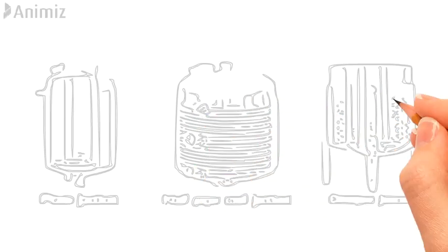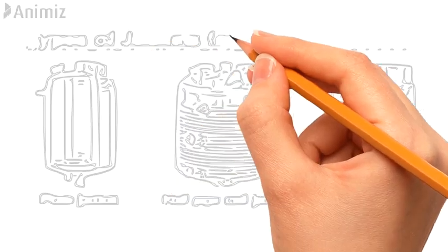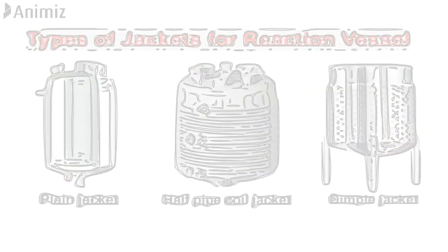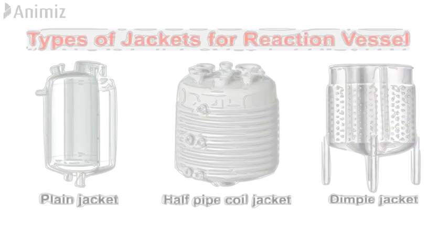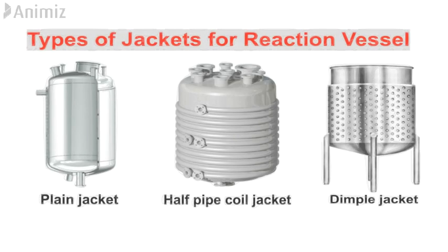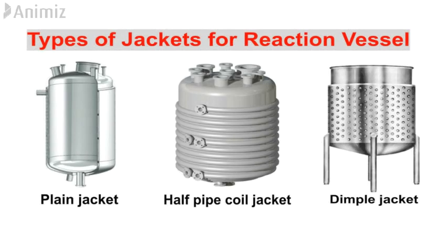Spiral baffling can be provided in the jacket. It helps to induce turbulence and increases heat transfer coefficient. Half pipe jacket: half pipe coil jacket provided optimal strength and rated to 750 psig (54 kg per cm²). In addition, half pipe jacket are recommended for high temperature industrial processes and all liquid heat transfer applications.